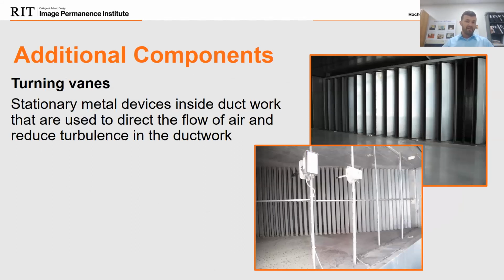One is a turning vane. They look similar to dampers, but obviously there's no way to adjust them. They're in a fixed position. They're mainly used to direct the airflow, so the air is not as clumsy as it moves through the ductwork. Most of us have been in a space where you've heard the air turn on and you hear the loud banging. Sometimes that could be the clumsy air moving through the ductwork, as they call it. In this scenario, the vanes are to help guide the air through the ductwork so it's not as loud or noisy.